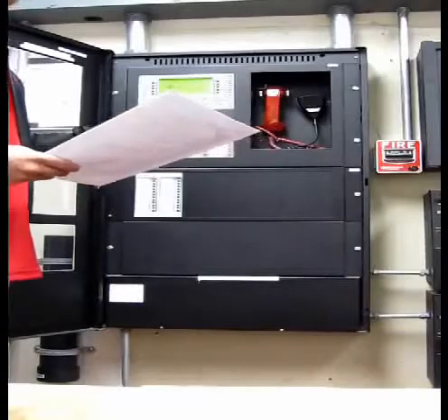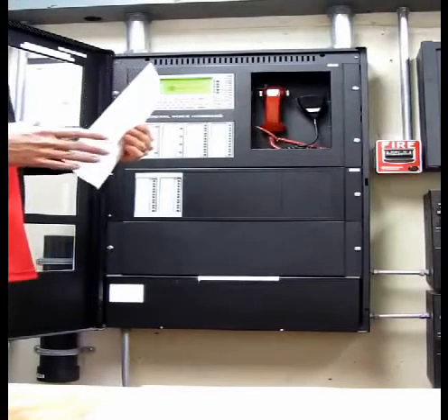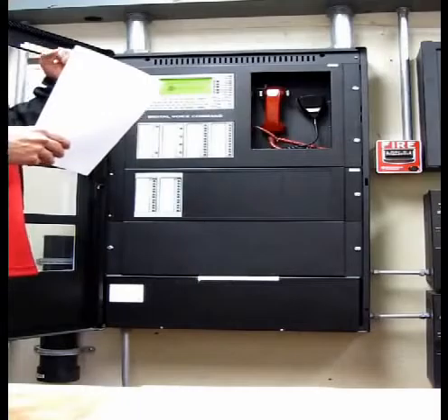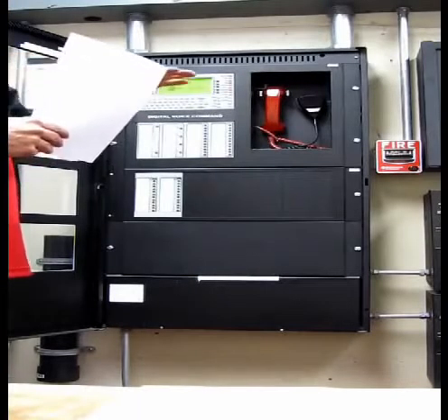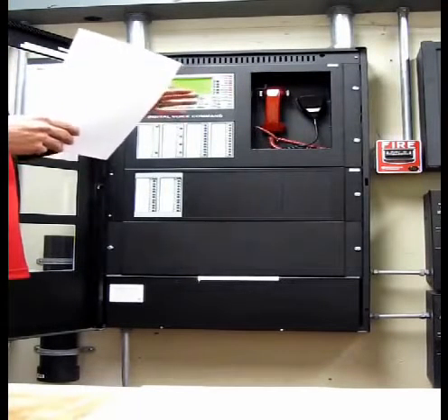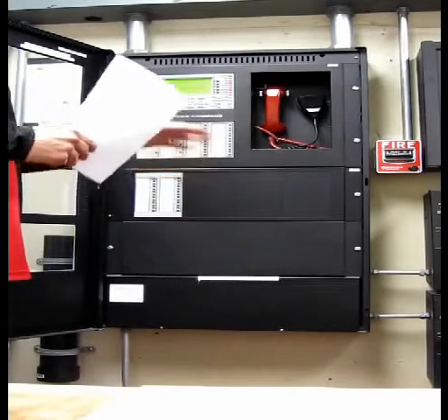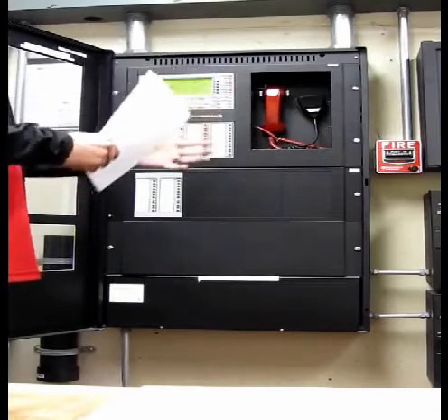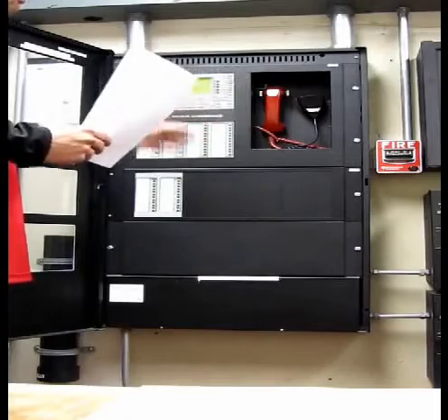Now, a big thing I want to go over, because a lot of people ask me this question, I'm sure you guys know it, but when you put a system on test via the phone from the central station, it doesn't disable all the smoke detectors in the building. It's basically just telling us not to call the fire department if there is an alarm. Every time. So you still have to cover up the smokes if you're doing any kind of welding or soldering or painting.